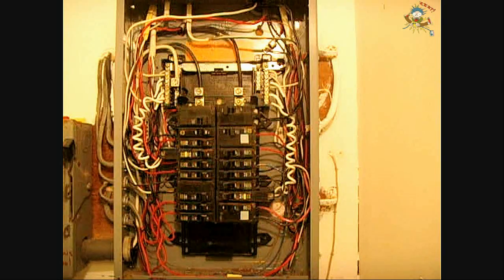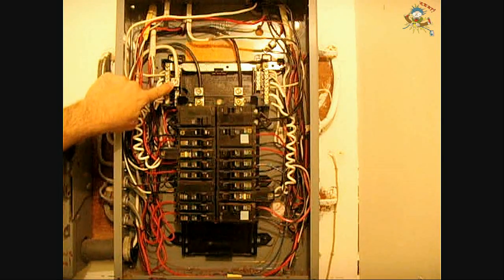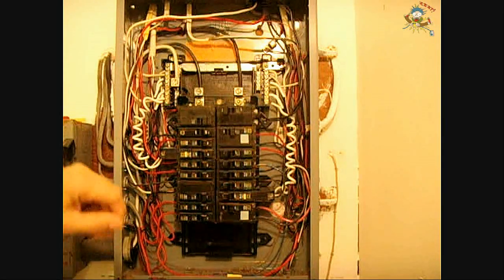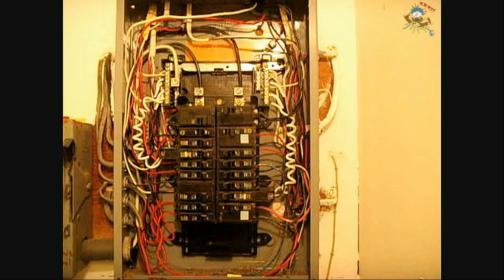On the power transformer, this connection here, which is the middle screw on the transformer, is also connected to earth ground. You'll see a wire running from that post on the transformer heading straight into the earth where it's connected into a copper rod. Now when these panels are connected up, there's 2 ways that they do it.